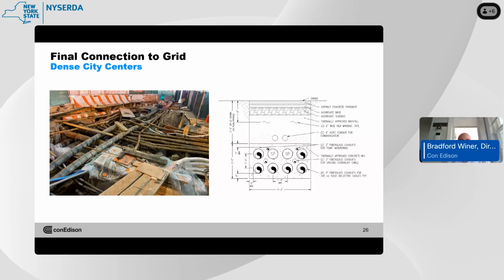This is just the duct bank. For each circuit you'll need bigger ones if you go with a double circuit, but for conversation we'll go with a single. You're going to need a 4-foot by 6-foot structured concrete box, rectangle, installed point to point, from the converter station to the substation.